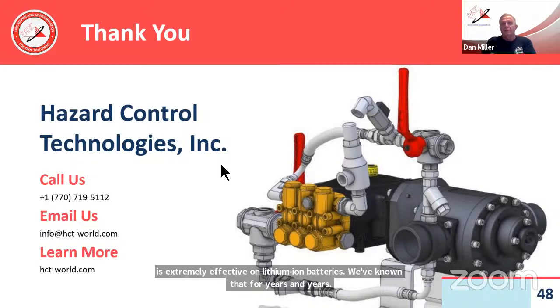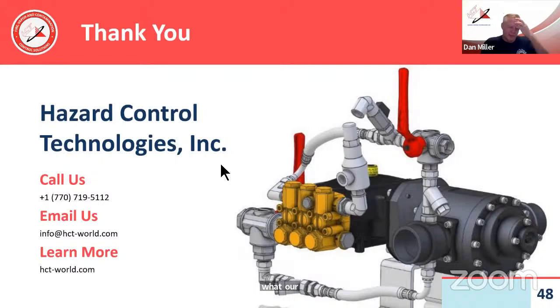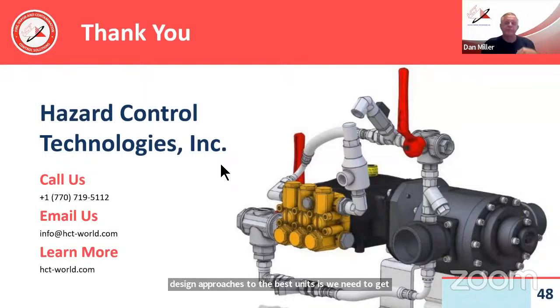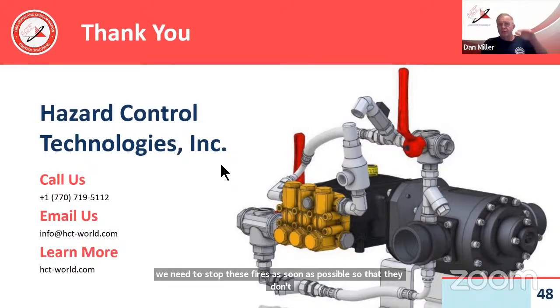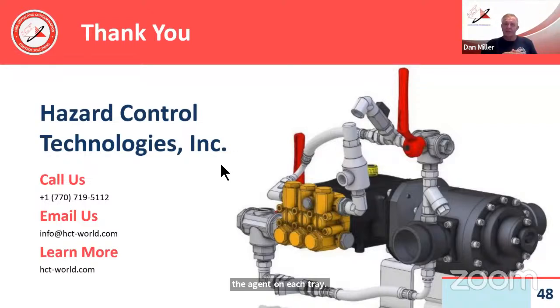Our design approach to the BESS units is that we need to get spray on each battery tray. If you think of a BESS unit like a server rack, a rack with a bunch of trays, each tray has some batteries. Those batteries are interconnected to make enough of a current flow and power over time. But we need to stop these fires as soon as possible so that they don't grow out of control in seconds. So we need to get the agent on each tray. And then because of the NFPA standards on passive fire protection between each rack, we need to get sprinkler protection for each rack and then for the overall unit itself. So it's kind of a triple level of redundancy. So tray, rack, unit, and we make sure we cover all contingencies there to keep it definitely to the unit level.